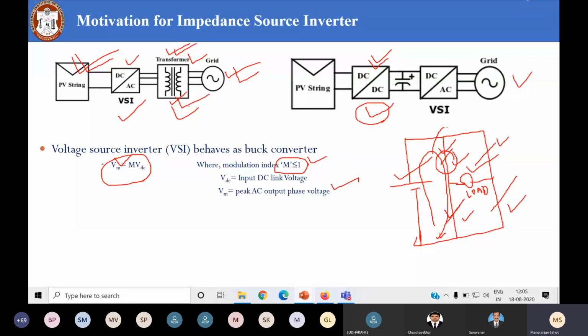The problem is this: whenever both switches are on, it creates a shoot through fault, called shoot through. It's a false turning on of both switches, which you don't want. But if you don't give a proper delay time, the upper switch may not have turned off properly by the time you give pulse to the bottom switch, so it turns on. This can short circuit the inverter leg, causing a shoot through fault. Because the resistance is very low, the current will be very high, possibly beyond the current rating of the switches and the source.